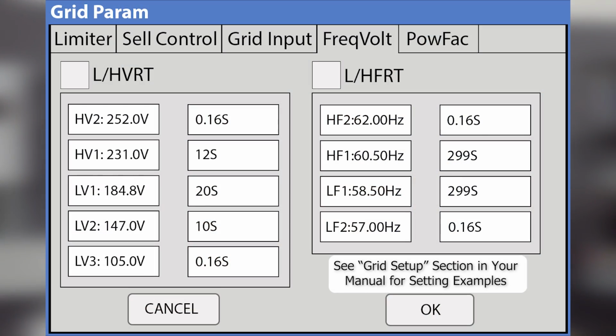Next up we have the frequency-volt tab. This is going to be used mostly in places like Hawaii, Puerto Rico, Bahamas, Virgin Islands, all that good stuff. A lot of the smaller grids require these settings. If they're required in your area—actually I think even Massachusetts requires these now. These are your frequency-volt, high voltage, low voltage, ride-throughs, and ramp rates. You can adjust these here. These are numbers you're going to get from your utility if you need them, you just make them match. We have reference material in the Sol-Ark manual as well, where you can look up things like the Puerto Rico settings or the Hawaii settings, and you'll be good to go. Just make it match.